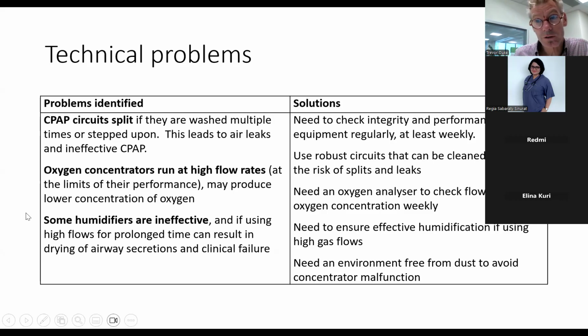The circuits these days are better than what they were. They were a harder plastic before, and now they're quite soft plastic. But sometimes when you're running an oxygen concentrator for delivering CPAP, you're running it at high flow rates, and that runs the concentrator to the limits of its performance. And that can sometimes lead to fatigue. The concentrator can become fatigued. So you need to do two things. One, don't run the concentrator to its limit of performance. And aim not to run it at 10 litres per minute, because that will lead to it being fatigued.